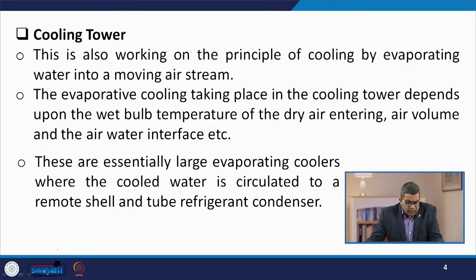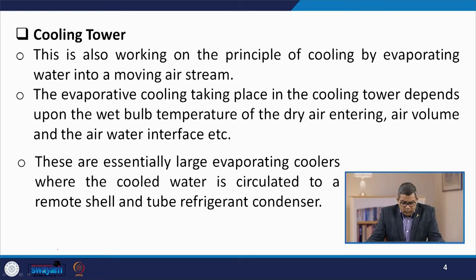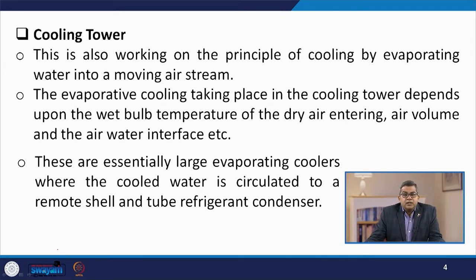Let us talk about the cooling tower. Although in a separate lecture we had an exhaustive discussion about cooling towers, they are also an integral part of the refrigeration system. The cooling tower works on the principle of cooling by evaporating water into a moving air stream. This evaporative cooling depends on the wet bulb temperature of the dry air entering, air volume, and the air-water interface.